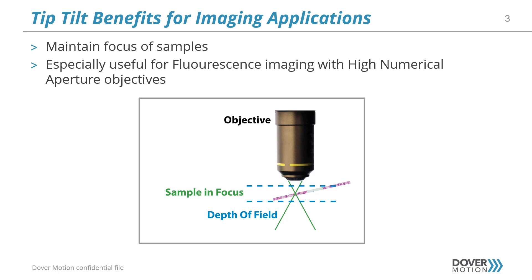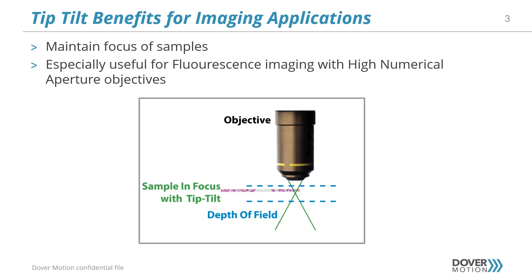As the sample is moved in XY, you can see it moving outside of the imaging depth of field. Adding a tip tilt stage allows compensation for this variation and brings the sample back into focus.